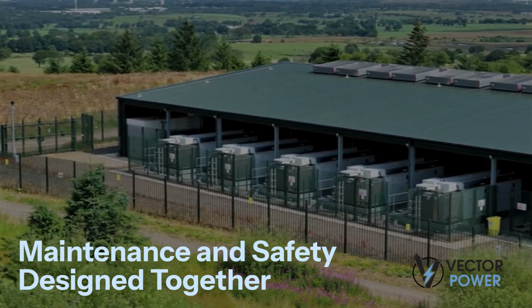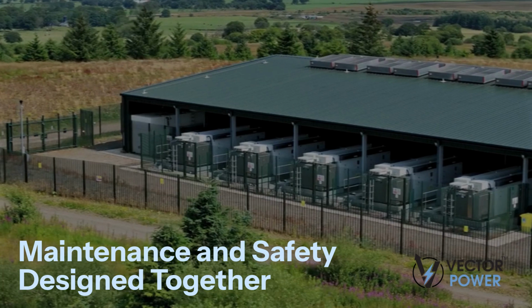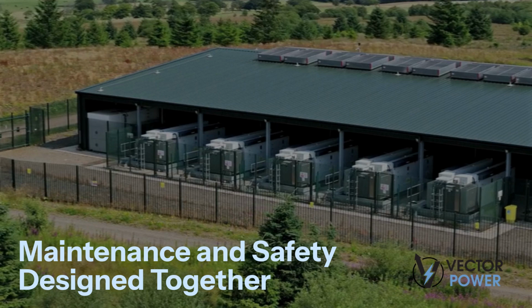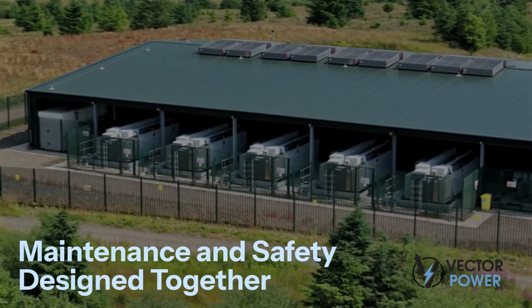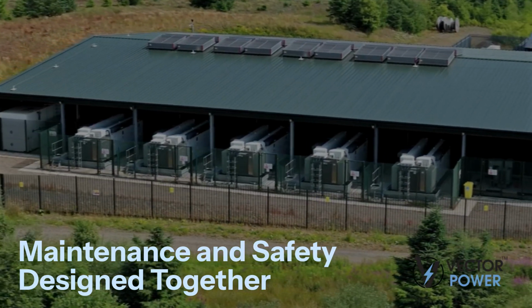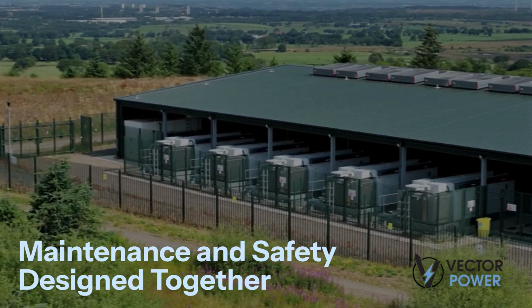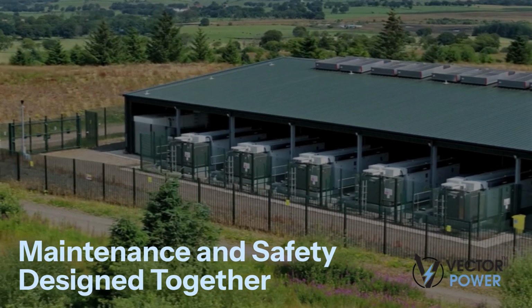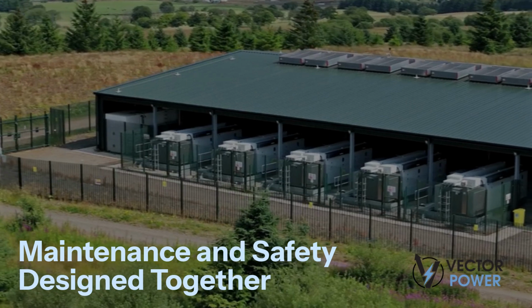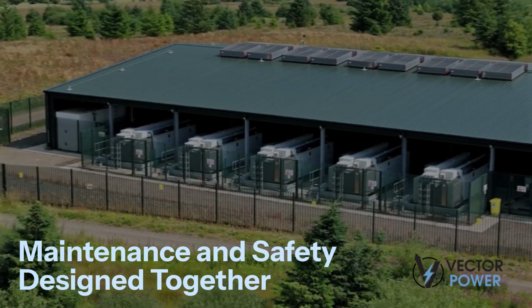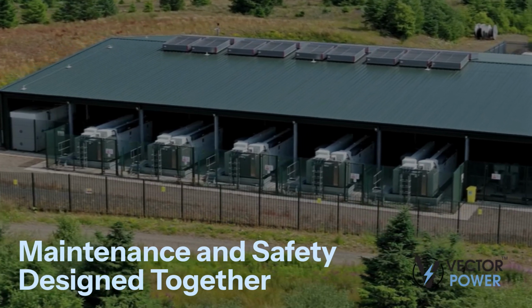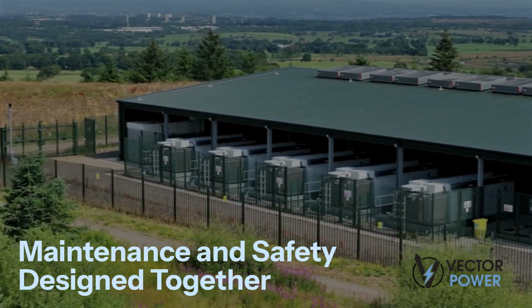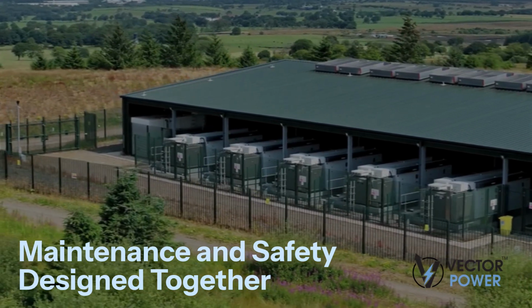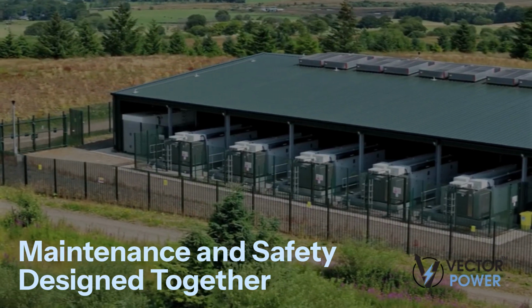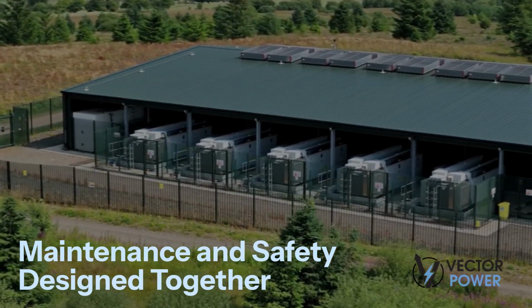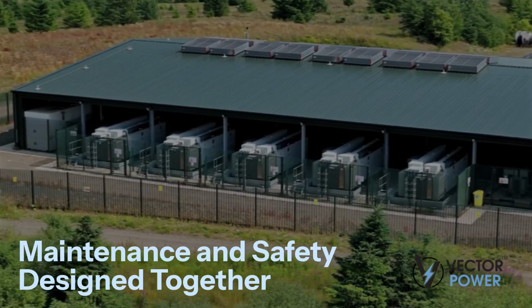Battery energy storage system hazards are multidisciplinary. Electrical hazards include shock, electrocution, arc flash, and arc blast. Chemical hazards include corrosive electrolytes such as sulfuric acid, potassium hydroxide, flammable solvents, and toxic off gases. Thermal and fire hazards include overheating, thermal runaway, fire spread between cells and modules, and explosion. Systemic hazards include control failures, communication loss, defective protective settings, or unsafe work practices.